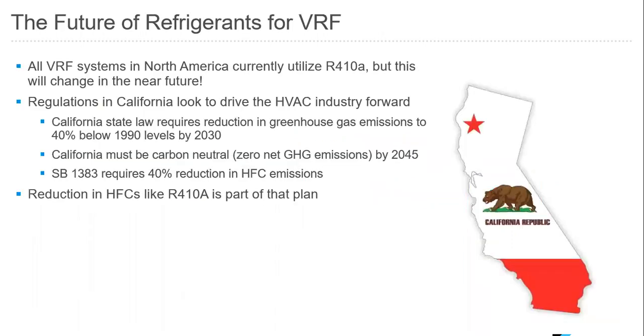So what is the future of refrigerants? Over the next several years, all of the HVAC manufacturers in North America are going to be asked to start looking at other refrigerants. And so currently everyone uses R410A, but that will change. Regulations in California are looking to drive the HVAC industry forward. So California state law requires reduction in greenhouse gas emissions to 40% below 1990 levels by 2030. One of the ways to reduce those greenhouse gas levels is to change refrigerants. And part of that is to reduce the use of HFCs such as R410A.